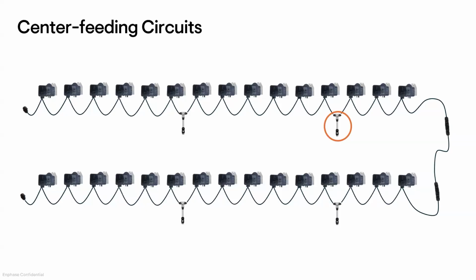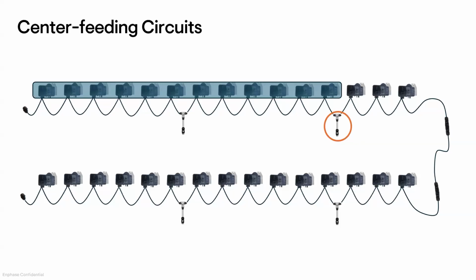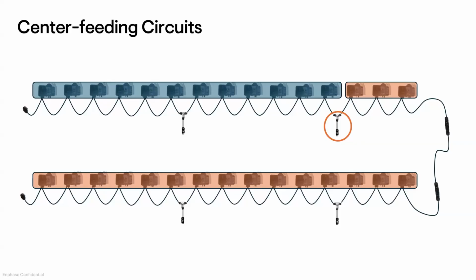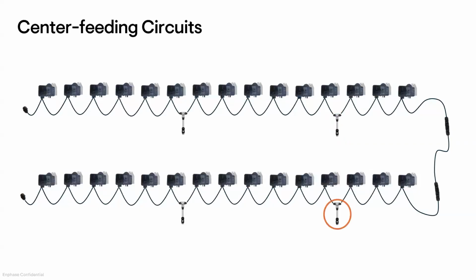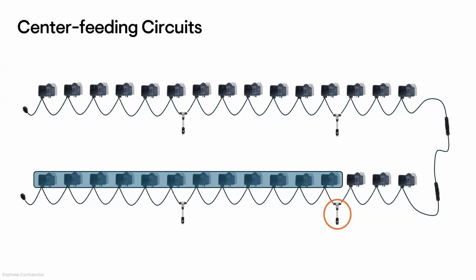So in this example, there are 2 options that you can choose because there are some limitations on the number of microinverters that you can have on either side of that center tap connection. So we want to have no more than 18 microinverters on either side of any center tap we choose. So like I mentioned, in this particular layout, there are 2 different choices. This first one is on the top because we'll have 12 microinverters on the left side of that center tap and 18 on the right, which completes that fully loaded circuit. So you don't have to have it exactly in the center. You don't have to pull your home run from exactly in the center. It's as close to center as possible without having more than 18 microinverters on one side of that connection. That other example is the one directly below that. Again, it gives you 12 on the left and 18 on the right.